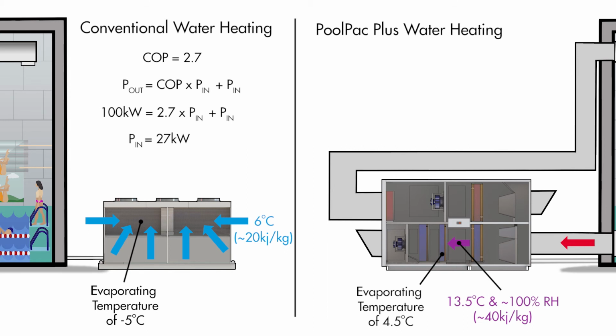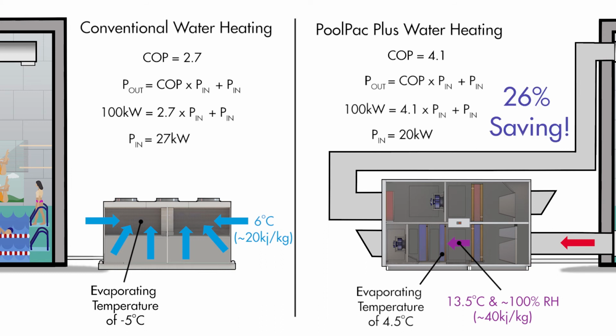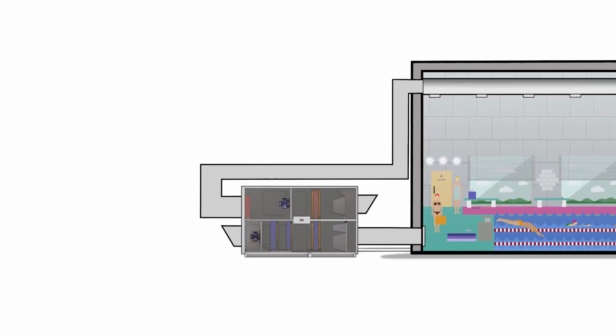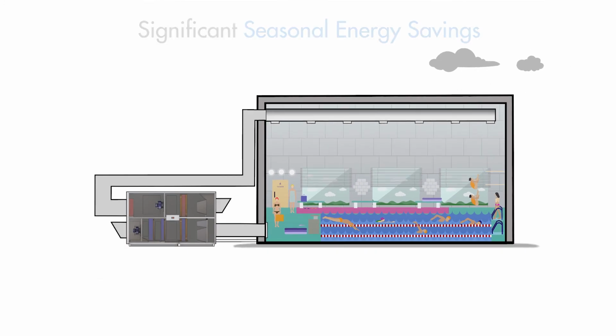This allows the evaporating temperature to be elevated to around 4.5 degrees Celsius instead of -5, which means the DX heat pump does not need to work as hard to transfer heat. And so, in this case we would expect a COP of something like 4.1, which would mean that the electrical requirement to produce 100 kilowatts of heating would be 20 kilowatts. This is a 26% reduction in electrical power consumption under these conditions. And although power savings are less profound in more mild conditions, they can still be seen for most of the year and translate to significant seasonal energy savings.